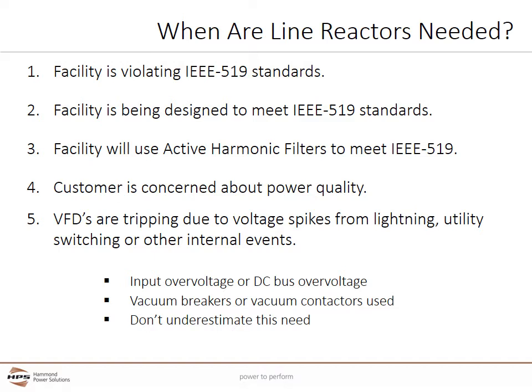Line Reactors are needed when the facility is violating the utility's IEEE 519 standards or when the facility is being designed to meet IEEE 519. Line Reactors are recommended to be used and coordinated with active harmonic filters.